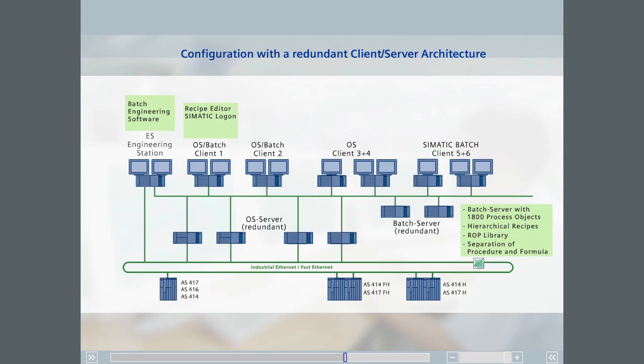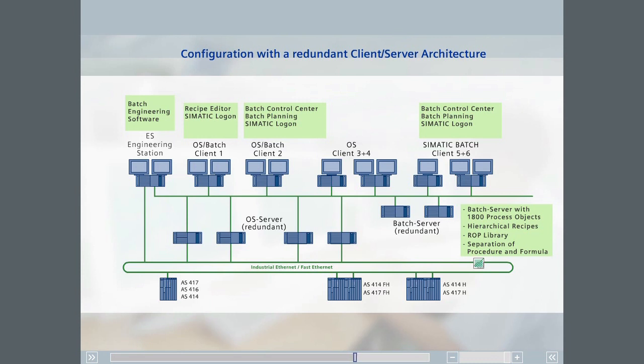Clients three and four are simply OS clients for operator control and monitoring of a part of the plant that is independent of SIMATIC Batch. Batch planning and control will be handled on clients two, five, and six. Here, in addition to the OS software and the batch control center, the batch planning option and SIMATIC Logon are also installed. Since access protection and electronic signatures are also required, the admin tool is installed on client two.